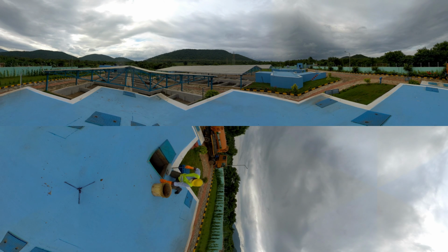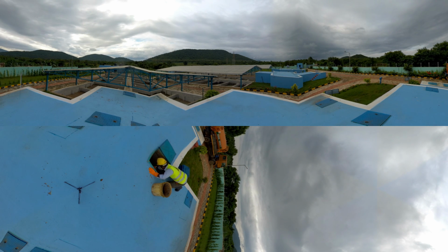Chamber 1 of the reactor should be checked for scum every time the sludge load enters the stabilization reactor. If there is scum present, then a fishnet mesh should be used to remove the scum into a plastic tray. Remember to deposit the collected scum into a plastic bin.